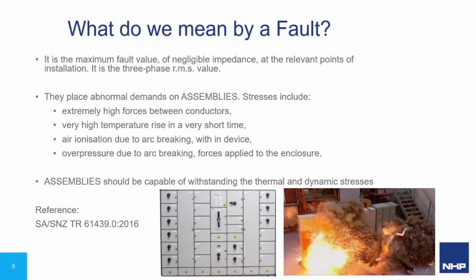The below is taken with reference to the technical report 61439 part 0. Short circuits within correctly designed systems are a very rare occurrence, but when they occur, they place abnormal demands on our assemblies. It lists some of the stresses: extremely high forces between conductors, very high temperature rise in very short times, air ionization, overpressure due to arc breaking. It goes on to tell us that assemblies should be capable of withstanding these thermal and dynamic stresses resulting from the short circuit.